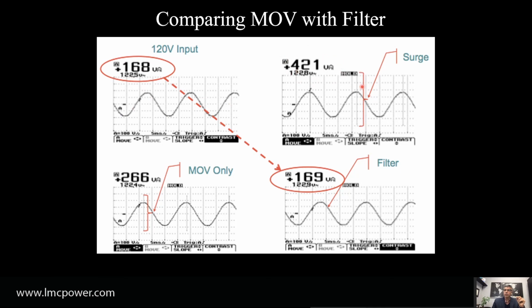Without this protector, those yellow cables were going to inject 421 volts directly into the power supply. But no, what we've done is the transient side of this equipment will attenuate, will reduce the voltage from 421 to 266. That way, it's reduced from a transient to a noise level. 266 is now considered a noise level. It won't burn the equipment. 421 may have burnt the equipment. 266 will just block the equipment, it'll create noise to the system.